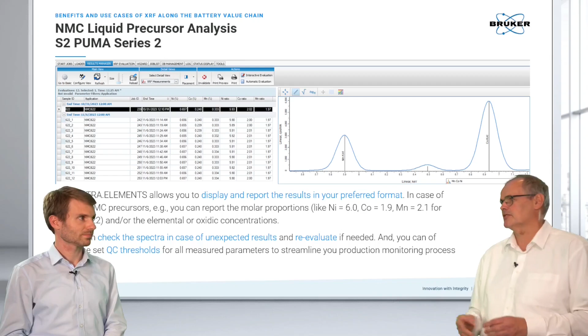The big advantage here we also wanted to point out: you see there is the spectrum shown, and whenever a sample is out of spec or you get a warranty claim that sample cells of a production batch might not perform as well, you are able to look at the spectrum and see if there is a contamination. So maybe the ratio is okay, but there might be a contamination which leads later on to performance issues. So you can evaluate all those spectra. They are stored in the instrument even after weeks. You can go back and see, oh, this batch had a problem, and you can evaluate if this was the precursor material you have used.